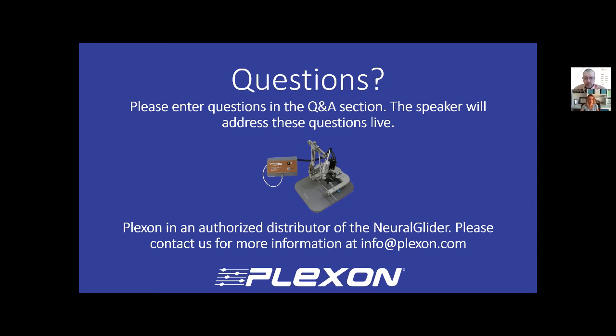Okay. What range of oscillation frequencies is most effective? Just to clarify, the actuator itself has a resonant frequency that can change just a little bit depending on what's connected to it. The control box is designed to find that resonant point, based on the impedance signal, so that it will always be vibrating at resonance, and that's typically in the 22, 23 kilohertz range. That's based on the transducer design we had for other projects, which then got adapted to here.